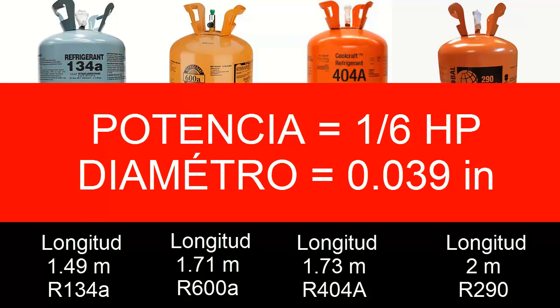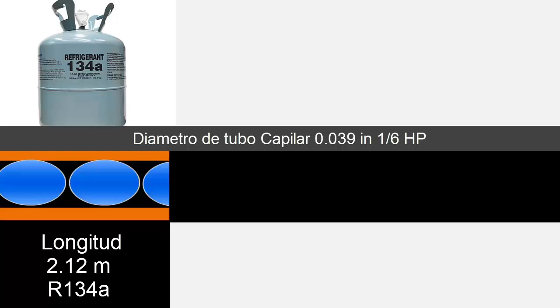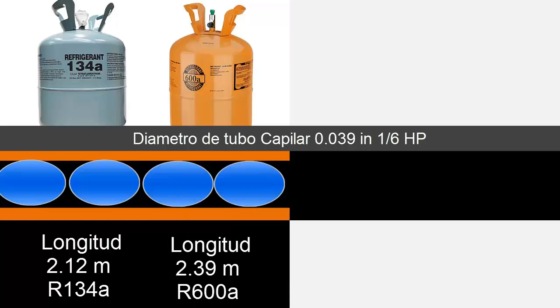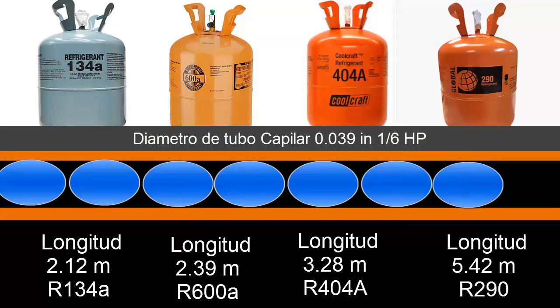Now let's move on to the electric power of a sixth horsepower. When we work with R-134A the length must be 2.12 meters, when we work with R-600A the length must be 2.39 meters, when we work with R-404A the length must be 3.28 meters, and when we get to R-290 the length must be 5.42 meters.